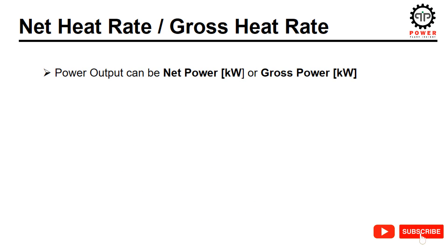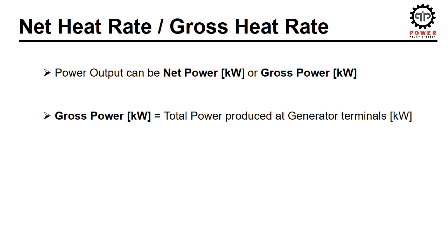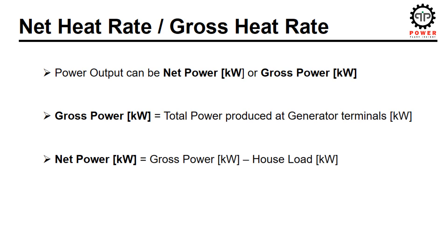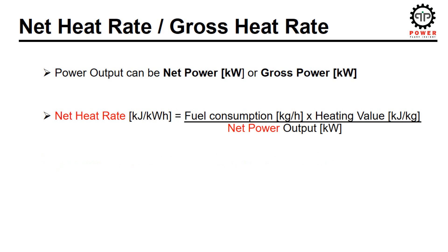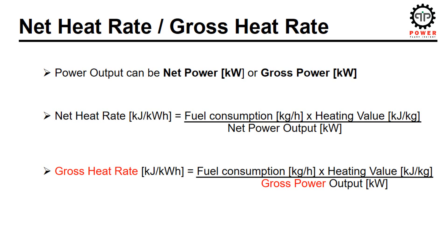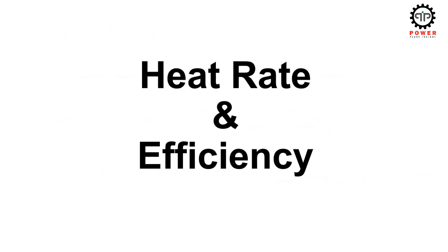Net heat rate and gross heat rate: there are two types of power obtained from a power plant — net power and gross power. Total power produced at the generator terminal is called gross power; it is the total power generation of the plant. Net power is obtained by subtracting the house load of the plant from gross power. House load is the in-house power consumption used within the plant for the operation of pumps, motors, and different auxiliaries. When net power is used in the heat rate formula, the result is net heat rate; when gross power is used, the outcome is gross heat rate.